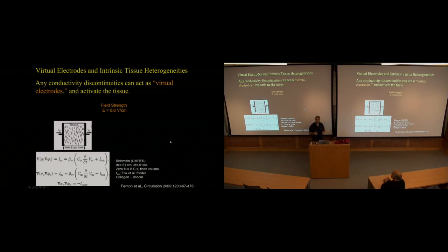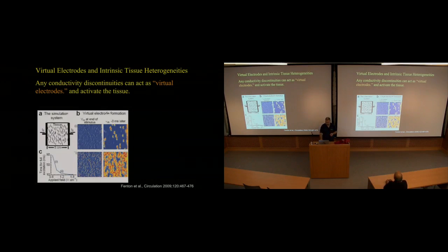So the idea is that instead of using one big shock, if we use multiple shocks just to slowly change the arrhythmia from one type to a different frequency, we can try to synchronize the system and terminate the arrhythmia. So this is the method we defined.